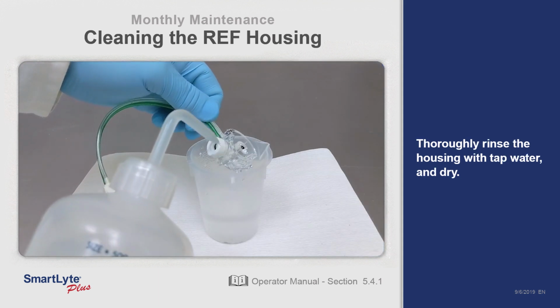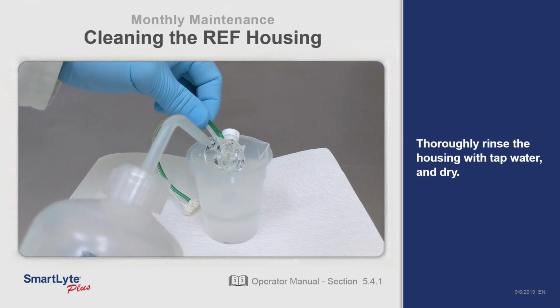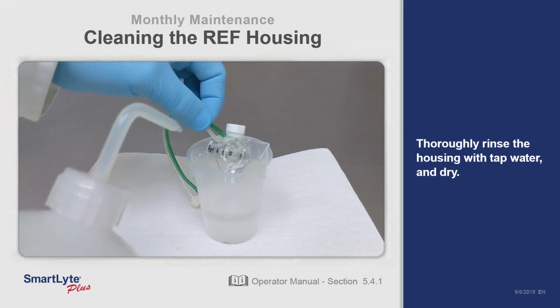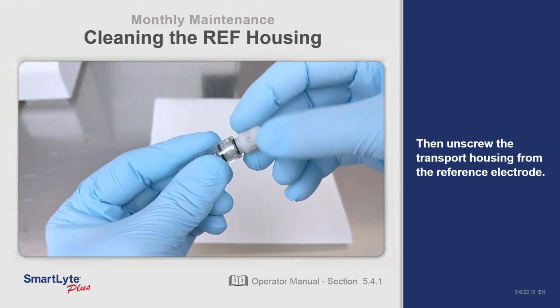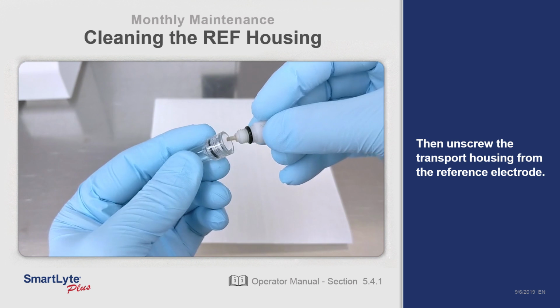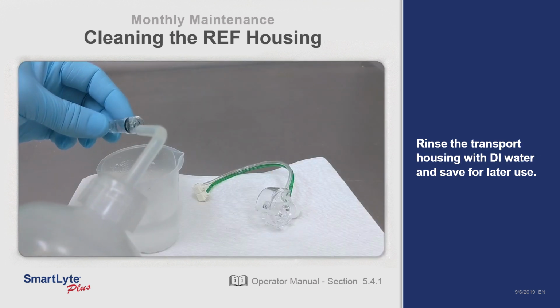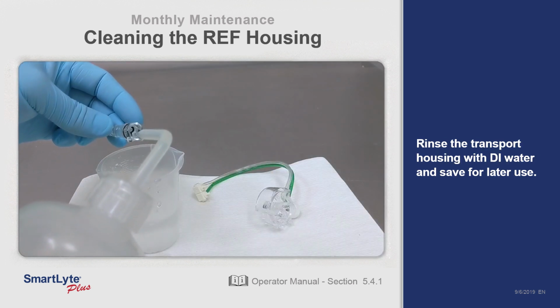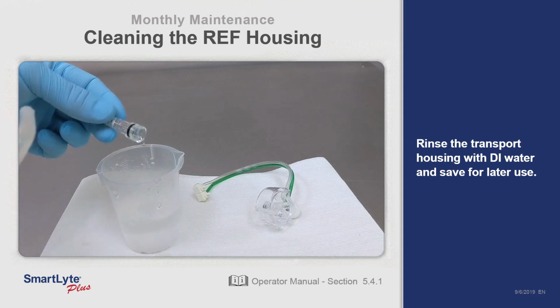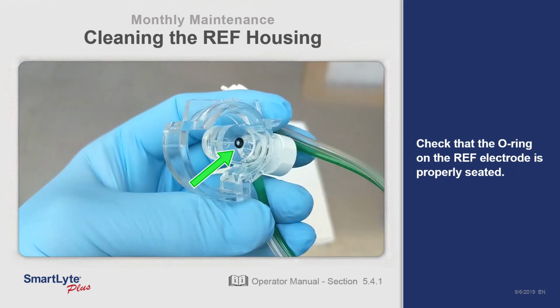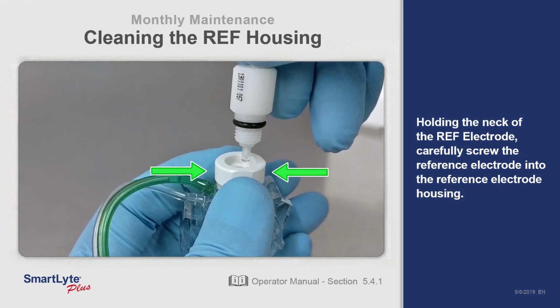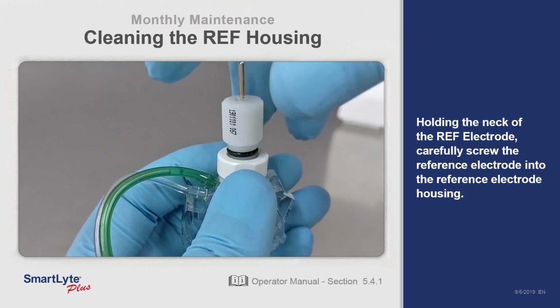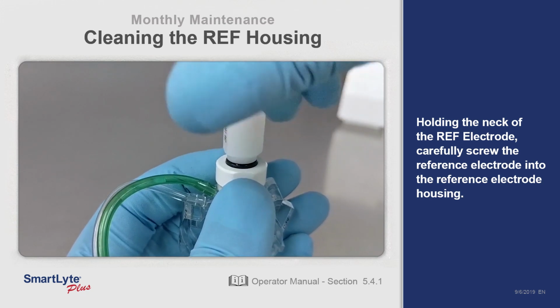Thoroughly rinse the housing with tap water and dry. Then, unscrew the transport housing from the reference electrode. Rinse the transport housing with water and save for later use. Check that the O-ring on the reference electrode is properly seated. Holding the neck of the reference electrode, carefully screw the reference electrode into the reference electrode housing.